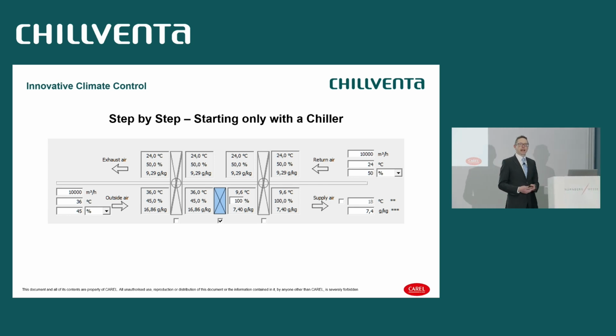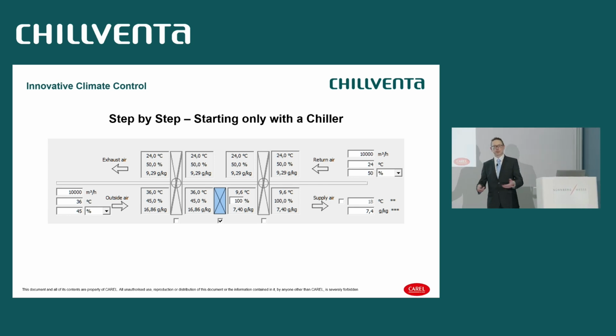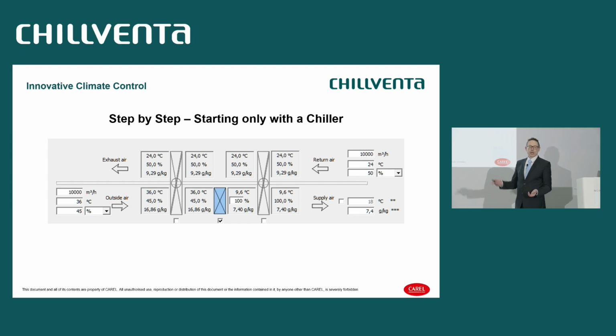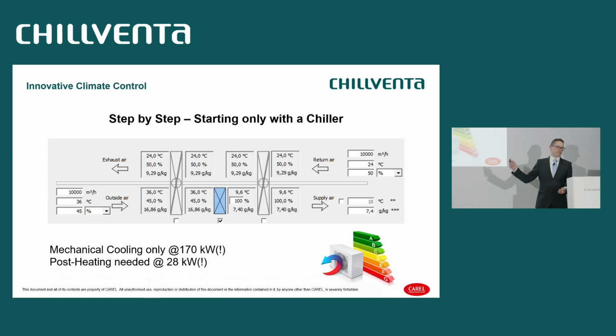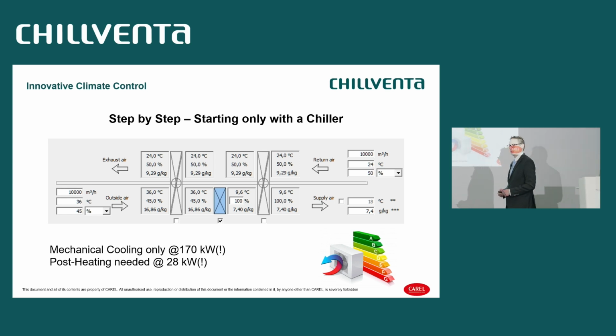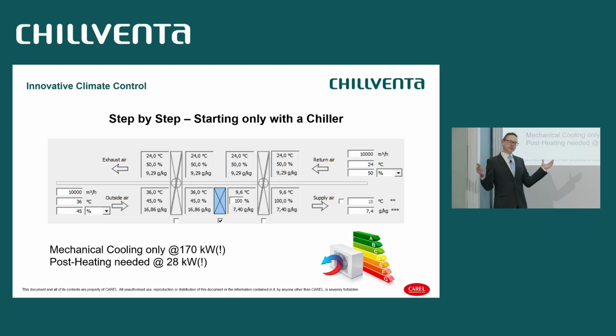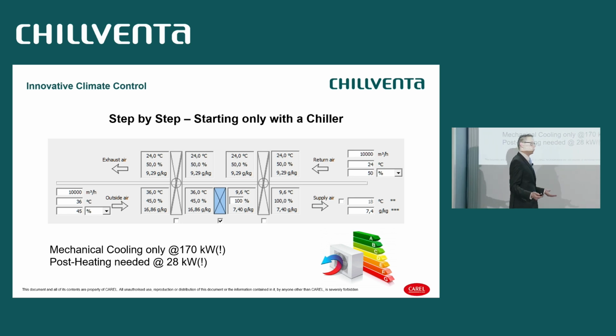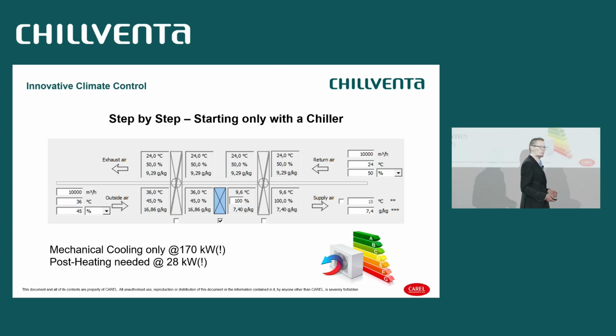Because inside the room you got heavy loads, like human people, computers, machineries. Here you can see mechanical cooling only. We are cooling down to roughly 9 degrees Celsius in order to force water condensing at the chiller. And to get to the temperature, you need to reheat it again. You have your target, whatever you need in your room, but you pay a price. The price is roughly 170 kilowatts chilling energy or mechanical cooling energy.